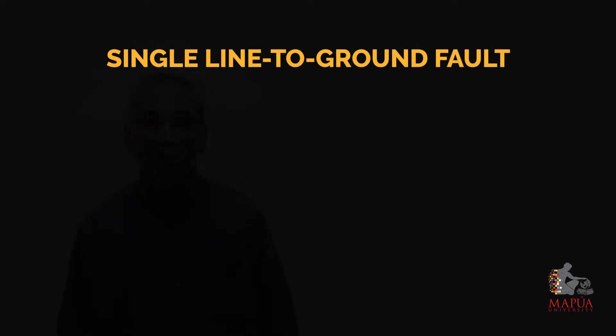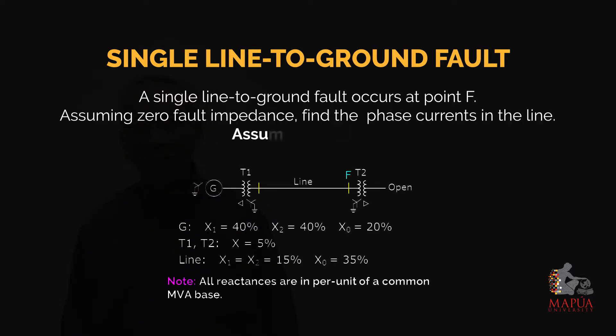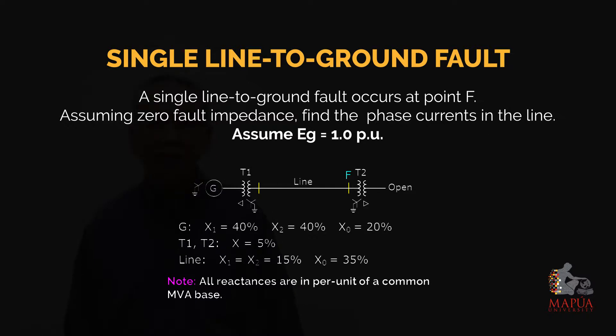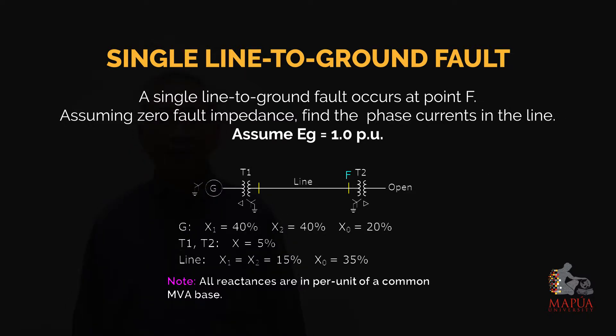This is an example of a single line to ground fault wherein there is a fault at point F. In the diagram we have one generator, two transformers, and a transmission line. The fault point is located at the end of the transmission line connected to the Y-grounded side of transformer T2. Assuming zero fault impedance, find the phase currents in the line assuming the voltage at the generator is equal to 1.0 per unit.